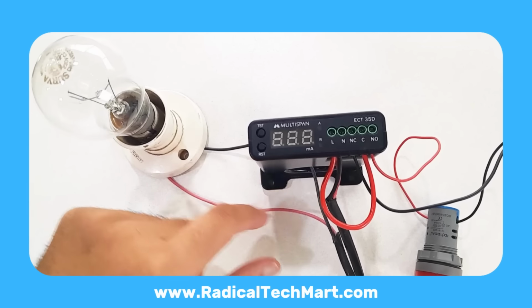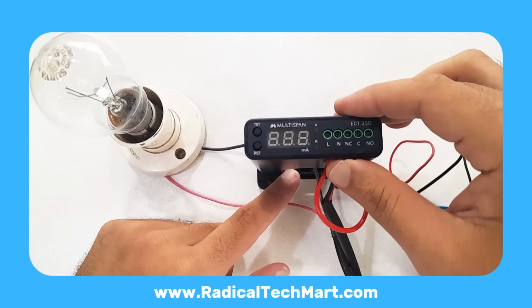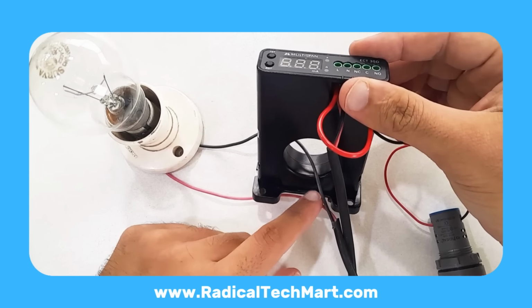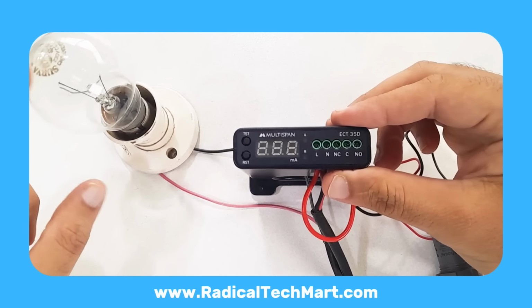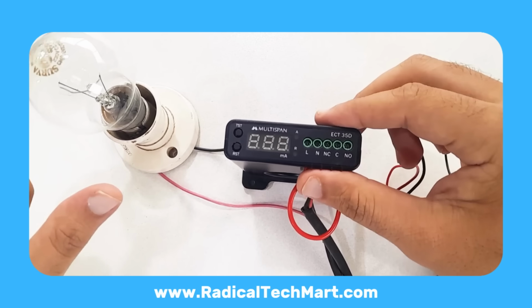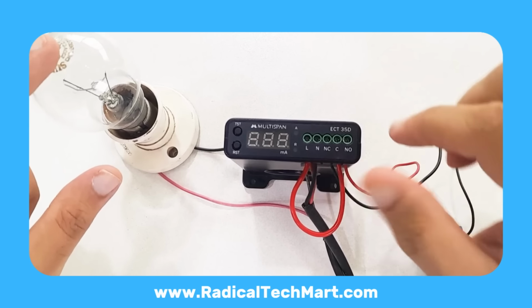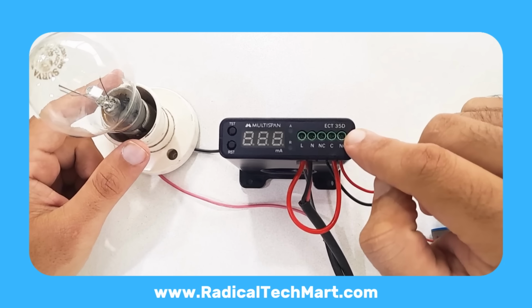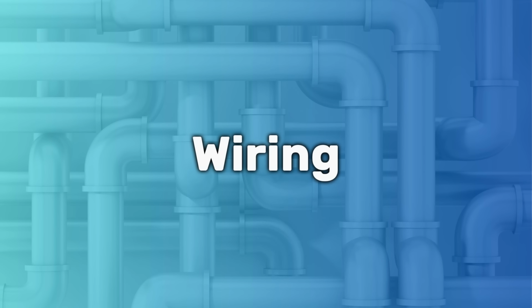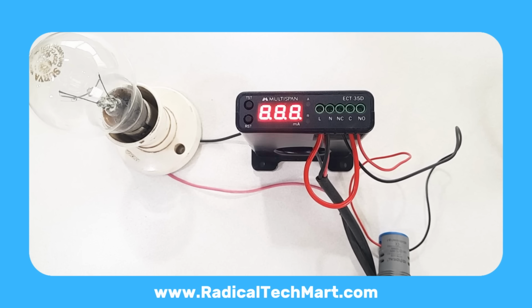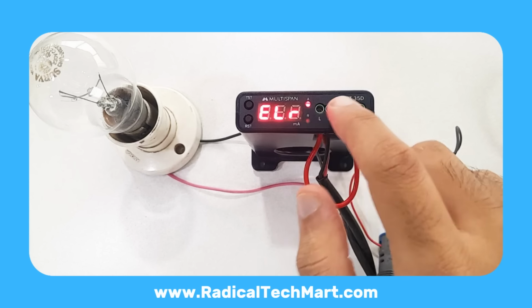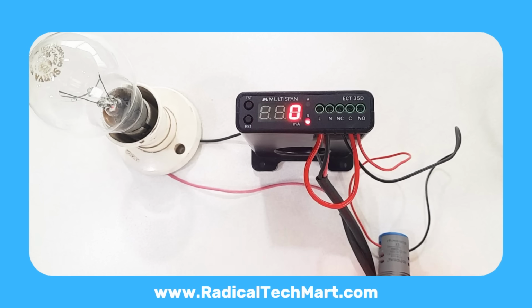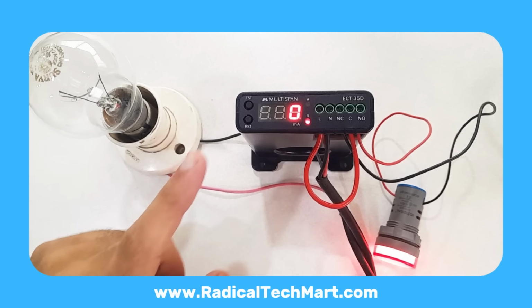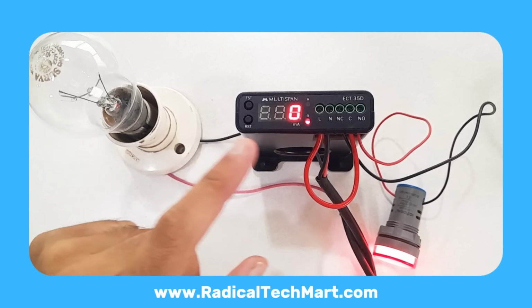The phase wire is connected directly to the bulb, while the neutral wire passes through the inbuilt CBCT loop before going to the bulb. So, whenever the bulb turns on, the controller will detect leakage current through the CT and trigger a trip action. Now, let's power on the meter. You'll see 0 on the display, and the relay LED turns on. Right now, there's no leakage in the system. That's why the display shows 0 leakage current.